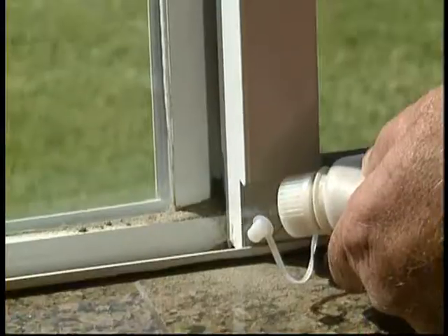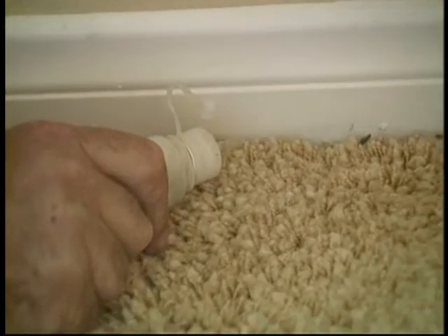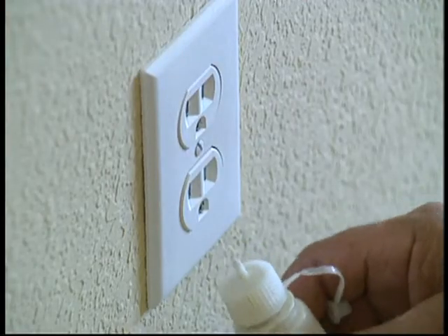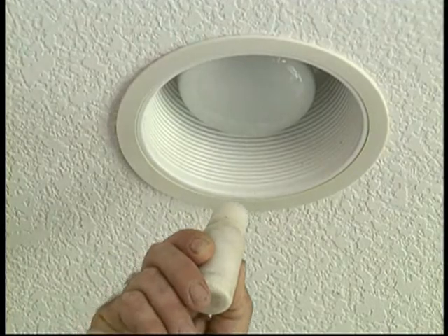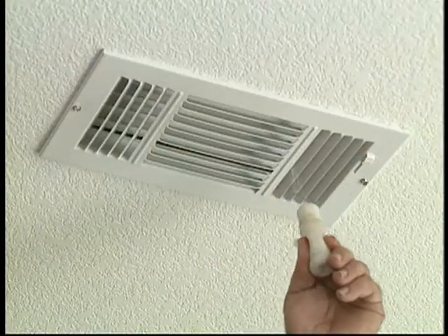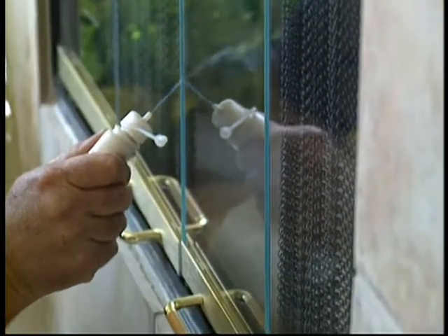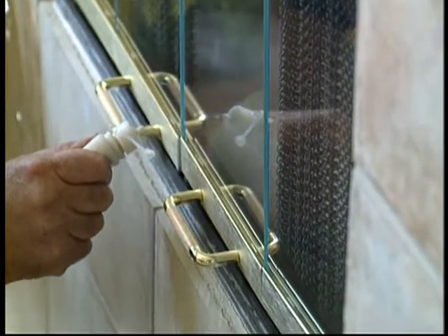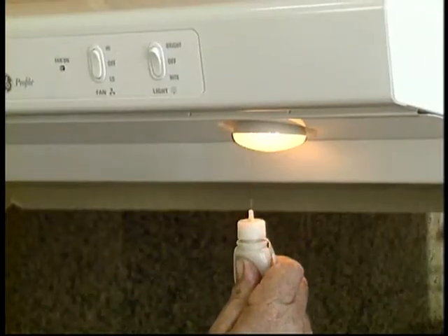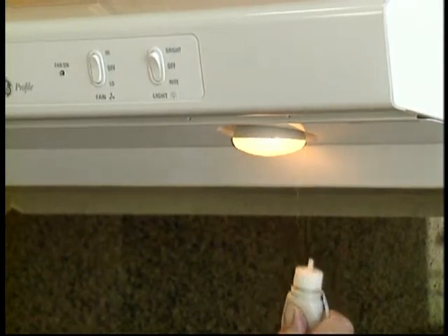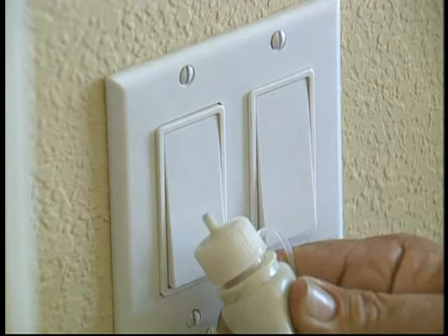The leakage sites are typically around the windows, around the doors, bottom plates, receptacles. A big one is ceiling lights. Ceiling lights leak a great deal. Dampers, duct systems. A huge one usually is fireplaces. The dampers are either messed up or there are a lot of places around the fireplaces themselves that leak a great deal of air. But with the visible smoke, when the house is pressurized and the air is blowing into it, we can pinpoint exactly where all the leaks are and correct them.